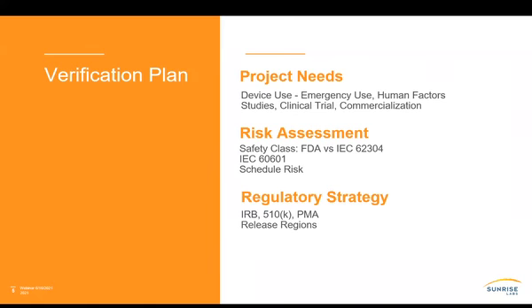Right, and here's a couple more questions. The FDA interpretation of 60601 versus 61010 for laboratory instruments. I don't know which one of you can grab that one. I can talk a little bit about it, and Tricia can fill in where I mistake. The biggest difference between 60601 and 61010 is in terms of the applied part. They're both safety standards, mostly electrical safety standards, and they go through a lot of similar clauses. But if you have a medical device that has an applied part, which is a part that would contact the patient, then you would need to follow 60601 versus 61010. I don't know if that fully answers the question or not.